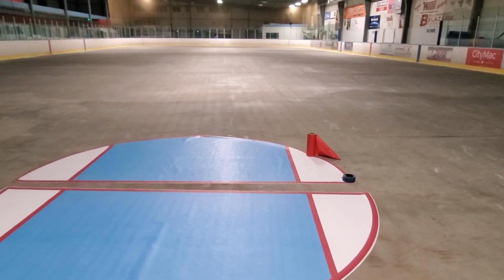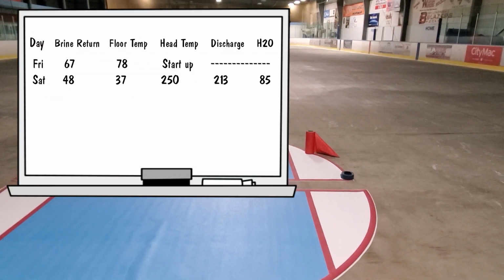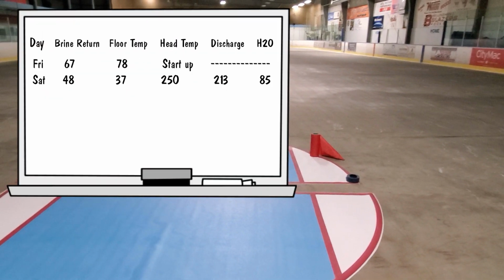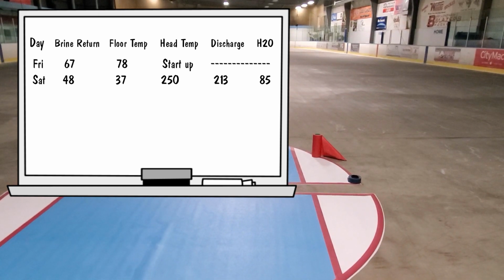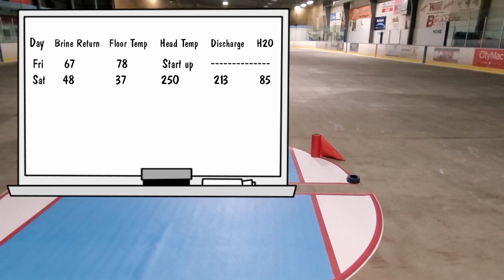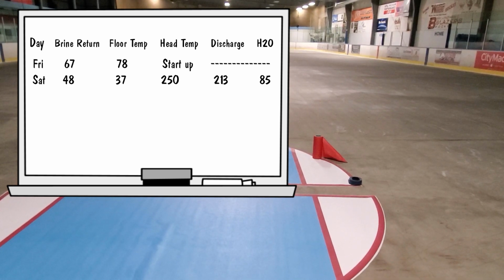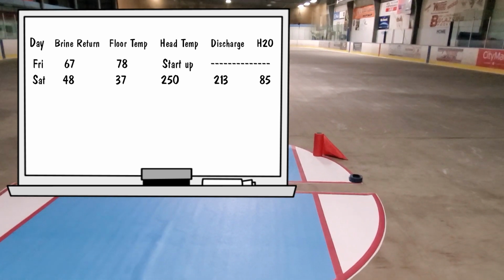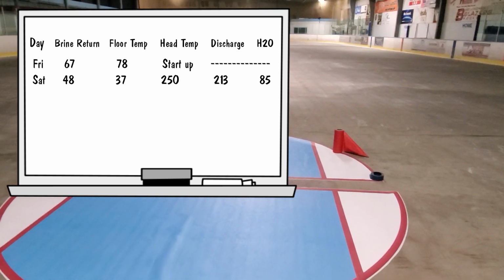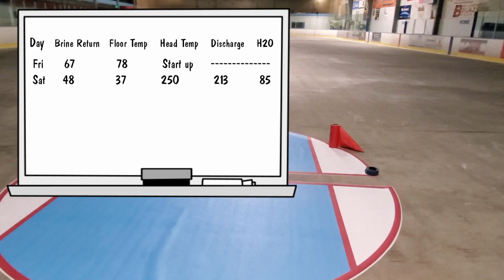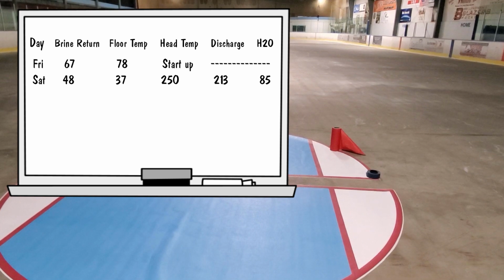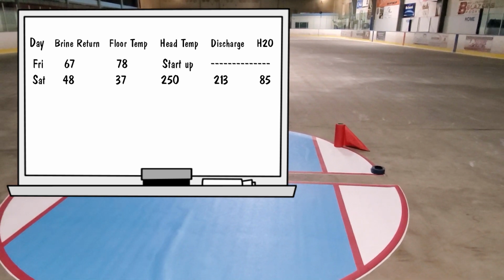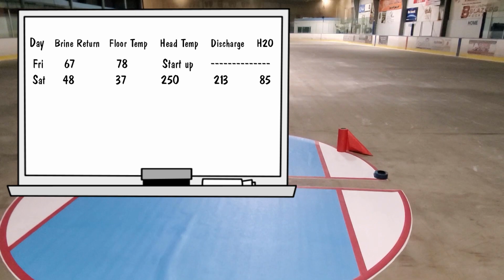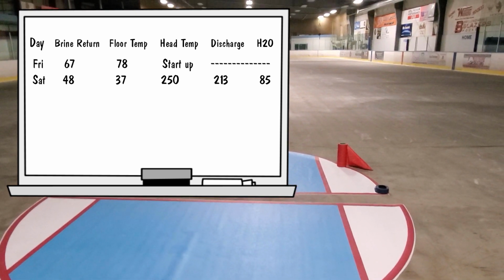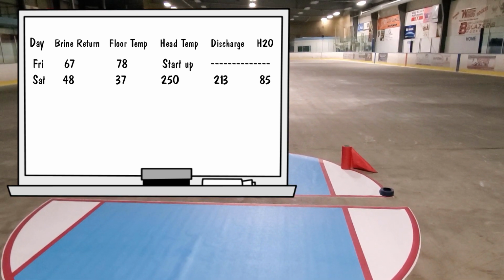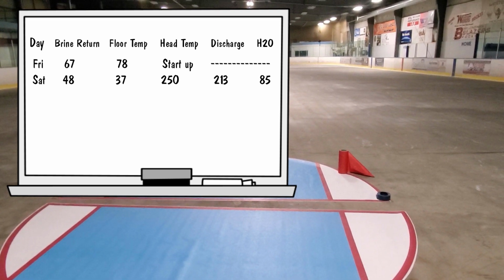So Friday, when we turned the compressors on, the brine chiller was at 67, and the floor temp was like 72, 73, maybe even as high as 78. So everything was going good. We left Friday, came back Saturday afternoon, and the temperature actually dropped quite a bit. The brine chiller was at about 48 degrees in the afternoon, and the concrete temperature was around 37 degrees. However, the head temperature was about 250, and that was really high. Anything over 200 is really, really high for at least our system.